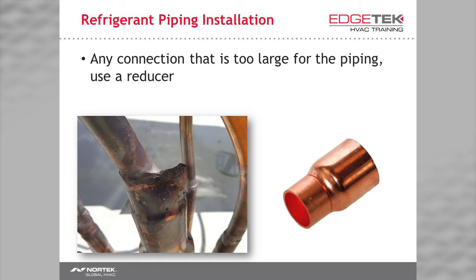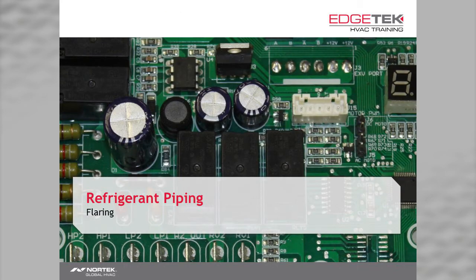Use a reducer. You may or may not know this, but most of our units have flared connections, just like mini splits. Often, flare connections aren't done right, so they'll leak. Then they'll be tightened some more, then they might break. People will use leak lock, they'll cuss, and they'll get mad. All of this can be prevented by flaring correctly in the first place. This has been a complaint since flares were invented. To see how to properly flare and what tools ensure 100% success, watch Proper Flaring Technique and Verifying a Proper Flare under HVAC Tips at edgetekhvac.com.